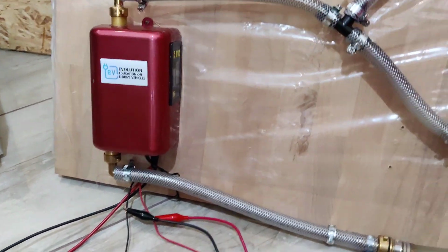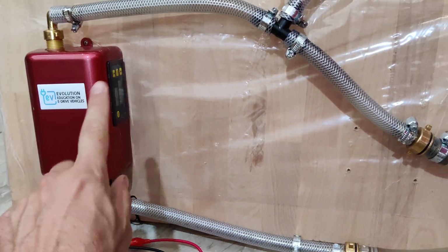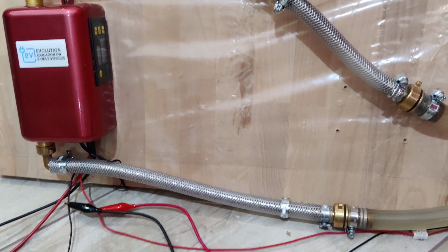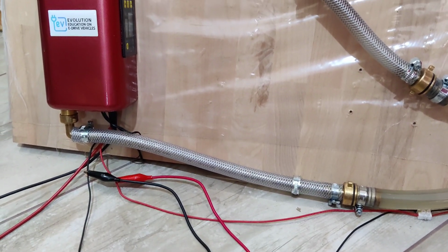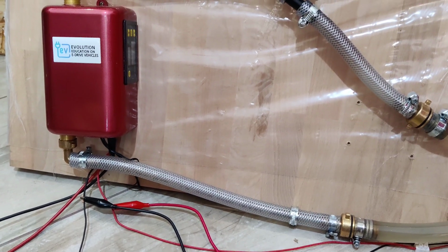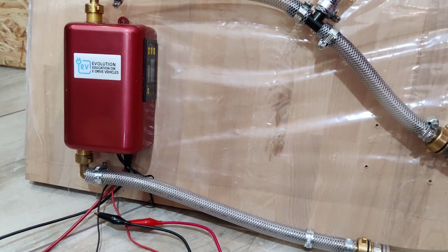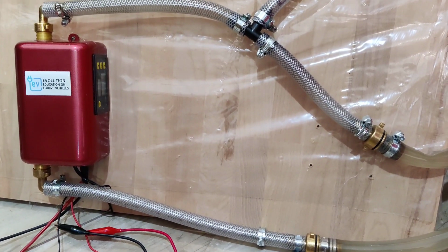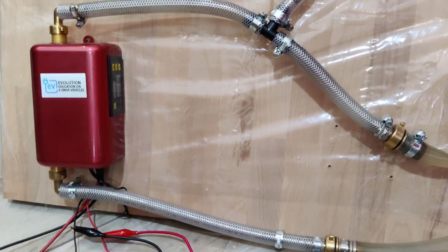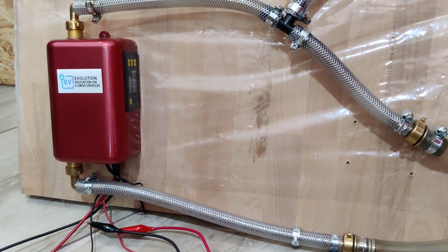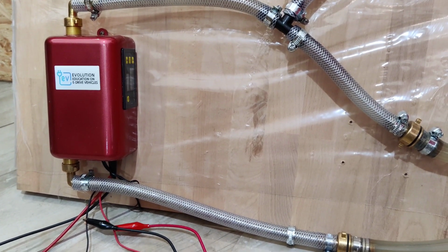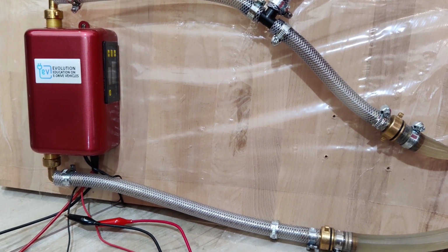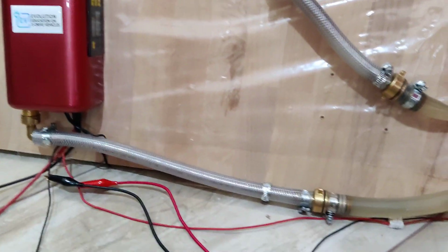That's because low voltage controls the heater and it cannot be activated without low voltage activating the relays and the thermostat that monitors temperature inside of the water heater. There are multiple security measurements inside. One is a thermostat. There is one more thermostat that makes sure that water doesn't boil out, and some other features.